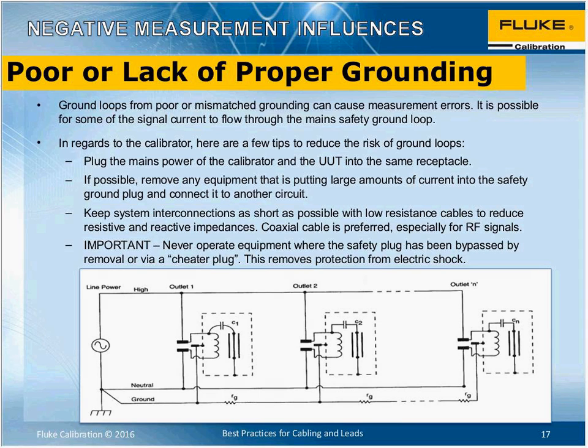The effects we don't really have time to explain to you in great detail, other than that currents flow in ground leads. Those can couple into our measurement circuits by various effects, and there's some good practice we're describing on this slide, where you can plug things from the calibrator and the unit under test into the same receptacle, very close, keeping them on the same circuit. Don't use different circuits that come from different breakers in the box. Don't have them on different phases if you have a 2 or 3 phase system. Keep those connections as short as possible, which means the impedance will be as low as possible. Make sure that you use, where possible, shielded or coaxial or twisted pair type cables that we've been talking about.